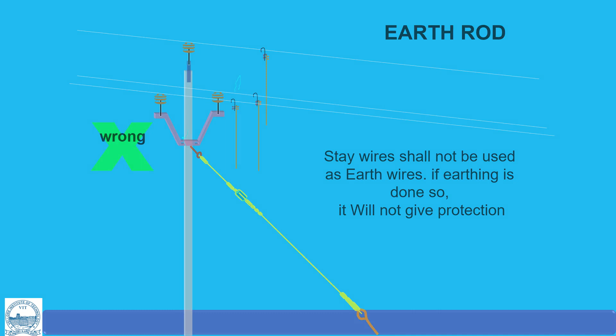Coming to the procedure for earthing, after discharging only, the earth rods shall be securely screwed, and then the rest of the line similarly. While removing the earthing, the earth rod shall be removed from the spot first, and after all the earth rods are removed, the connection to the earth pipe shall be removed finally. After removing the discharging rods from the supply, then only the earth rods must be removed. And the earths shall be placed in such a manner that they will not be detached inadvertently due to the movements of men or other causes. We should ensure that because of my movement, there is no disconnection of this wire.